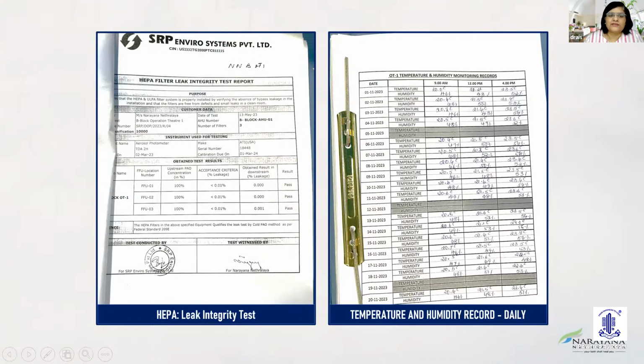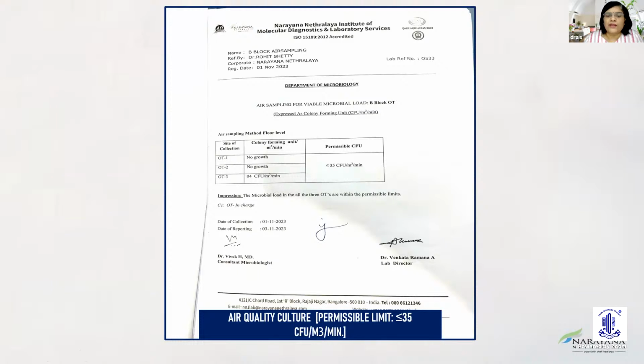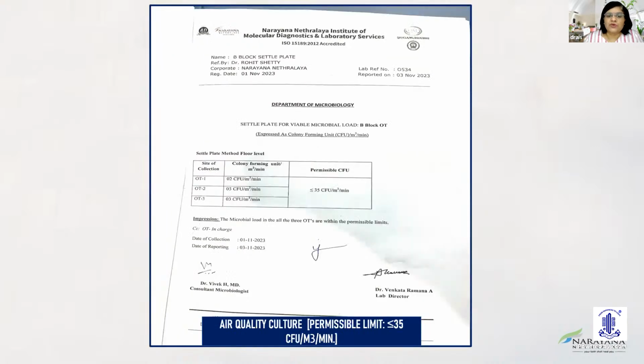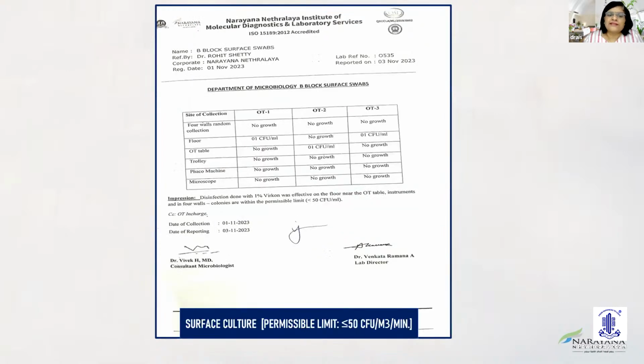Just to have a look, this is our internal HEPA leak integrity test and the temperature and humidity record, which is done daily. Coming to the air quality culture, our permissible limit is less than 35 colony forming units per meter cube per minute. This is also something we have for air quality culture, where the permissible limit is less than 35 CFU per meter cube per minute. What is important is that the surface culture is also done, say from the four walls or random collection, the floor, the OT table, the trolley, the phaco machine, the microscope. All these are very, very important cornerstones for us.